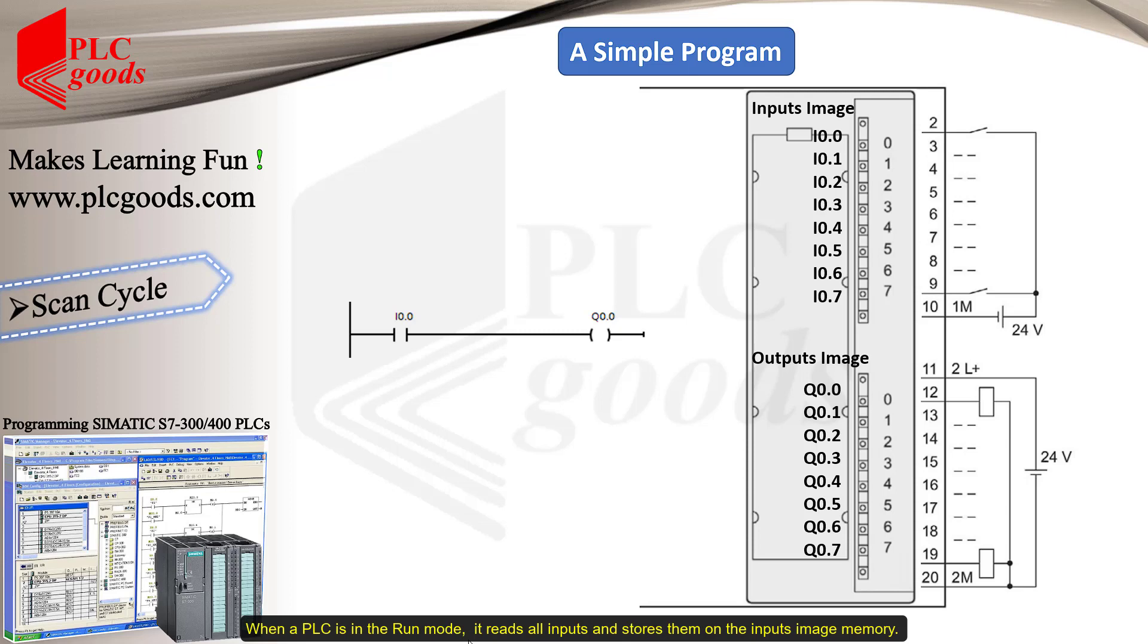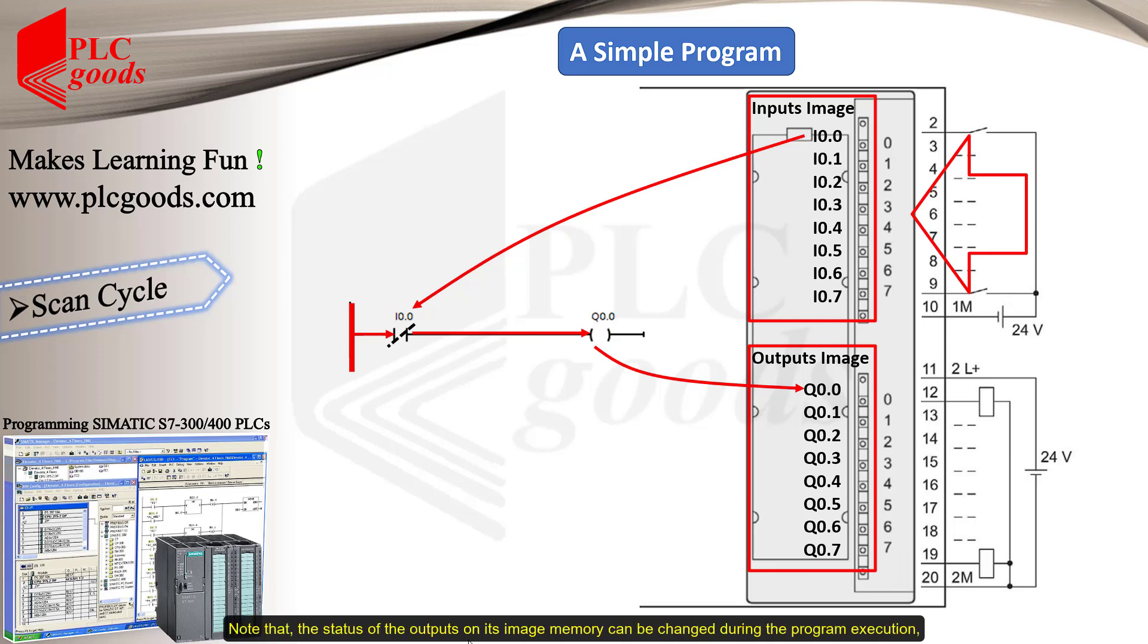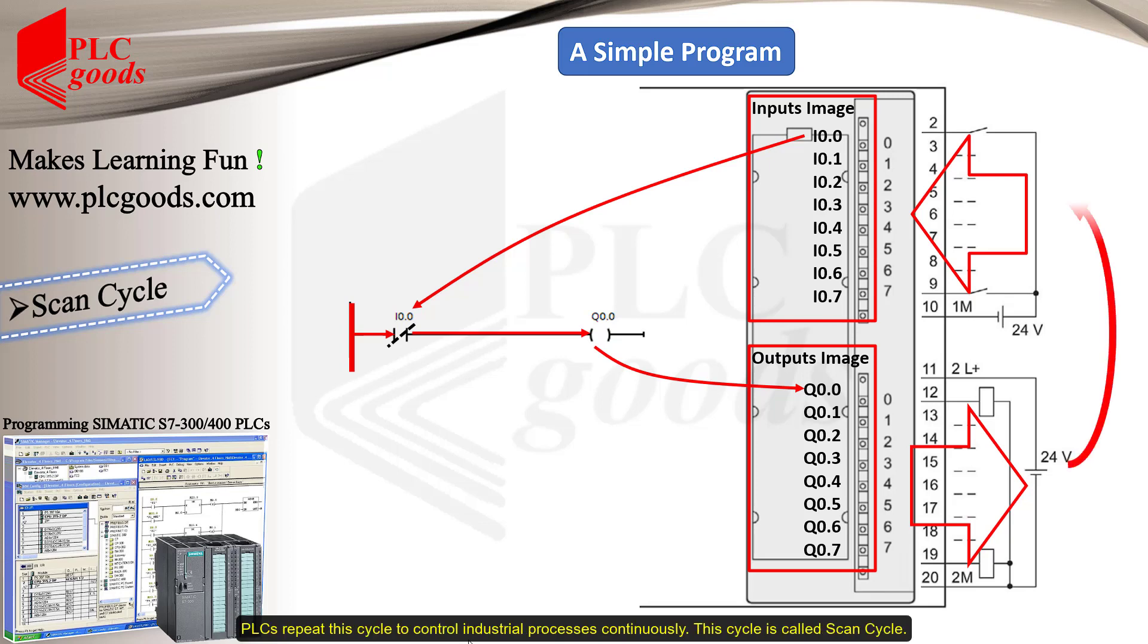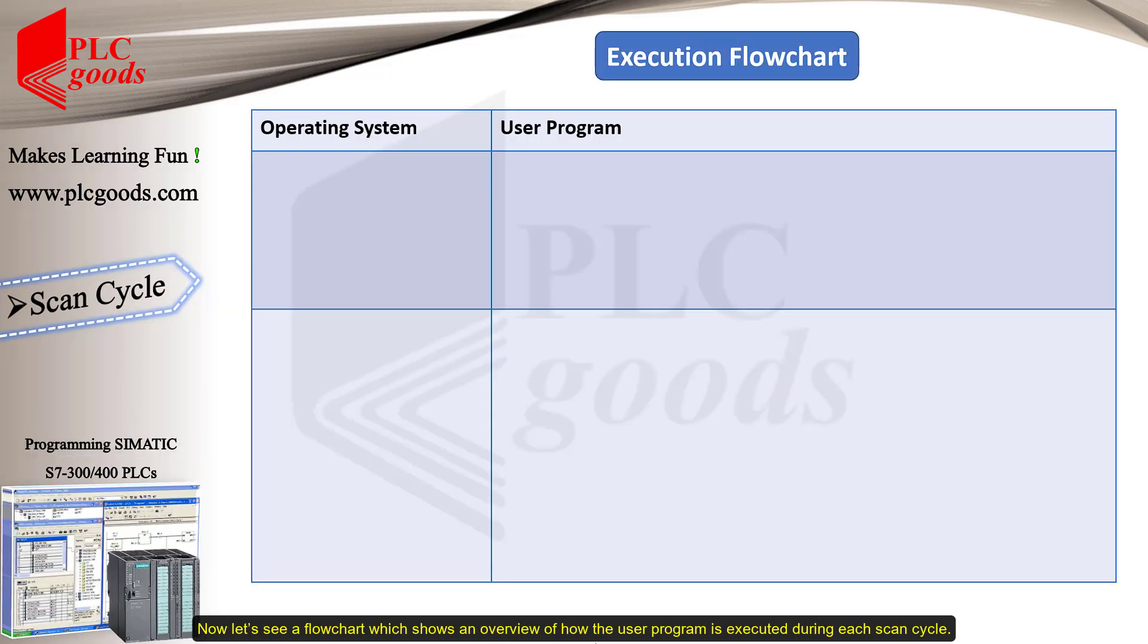When a PLC is in the run mode, it reads all inputs and stores them on the input's image memory. Then, the PLC executes its program completely to determine the status of all outputs. Note that the status of the outputs on its image memory can be changed during the program execution. But, the PLC updates the status of its connected equipment to its outputs when the whole program is executed. PLCs repeat this cycle to control industrial processes continuously. This cycle is called a scan cycle.